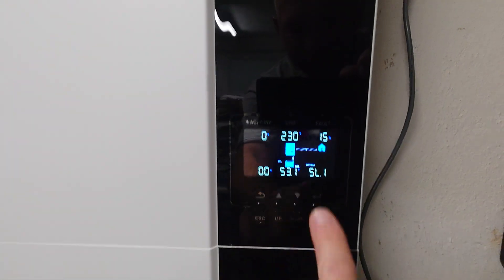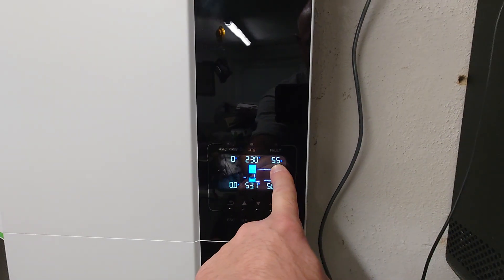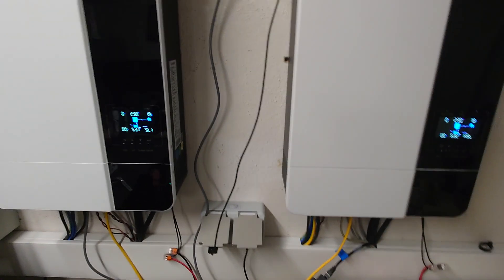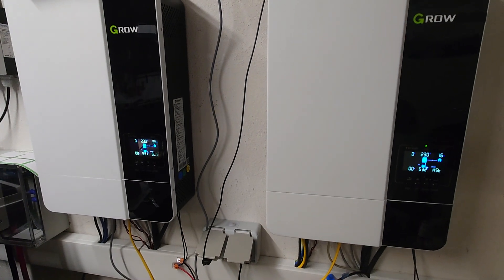You can see here the power is between 1.8 or 2 and 6. And the same here. If you listen carefully to the fans inside the inverters you will hear something — the fans are powering up and powering down, and this is really a killer for the fans.